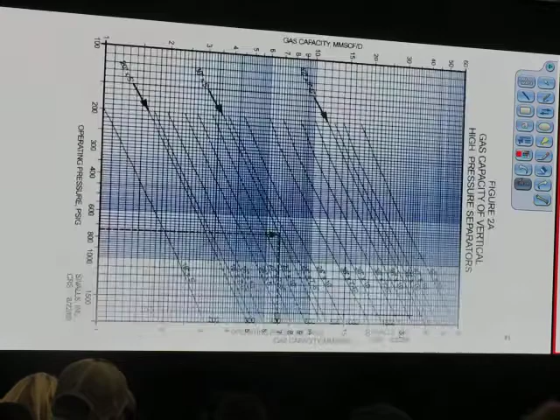Okay, now the question is, is that terminal velocity higher or lower than the actual velocity in the pipe? We should account for everything for the terminal velocity. You see this 0.85. Okay, we can calculate the gas capacity. Once we know the drag coefficient, put the drag coefficient over that. And this equation already takes care of those comparisons. This equation is derived based on the comparison between the upward actual velocity and the terminal velocity in the separator. Once I plug that in, this is the gas capacity equation for the vertical separator, I get that number.